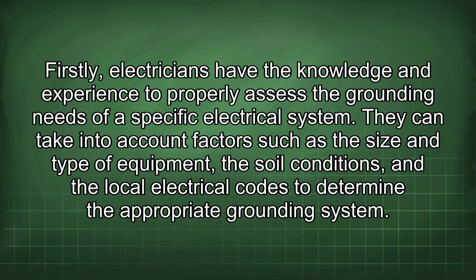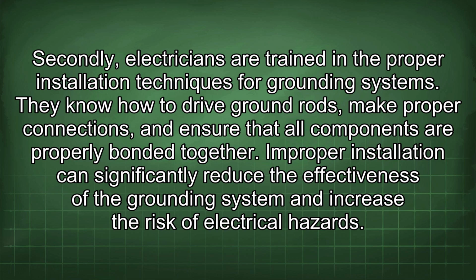Firstly, electricians have the knowledge and experience to properly assess the grounding needs of a specific electrical system. They can take into account factors such as the size and type of equipment, the soil conditions, and the local electrical codes to determine the appropriate grounding system. Secondly, electricians are trained in the proper installation techniques for grounding systems. They know how to drive ground rods, make proper connections, and ensure that all components are properly bonded together. Improper installation can significantly reduce the effectiveness of the grounding system and increase the risk of electrical hazards.